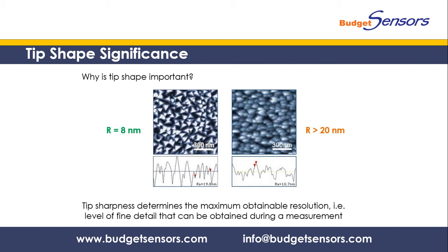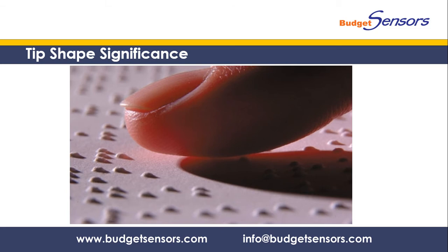Keep in mind that this tip with a 20 something nanometer radius is still a very sharp tip. It is roughly 5000 times sharper than a human hair. Still, it is not sharp enough to image this sample properly. So the sharpness of the small tip, at the end of the small cantilever, at the end of the small holder chip is what ultimately determines what we can see and eventually manipulate at the micro and nanoscale. A very illustrative analogy can be made with a blind person reading Braille code. This person will probably want to use their sharp fingertips to read rather than their elbows.